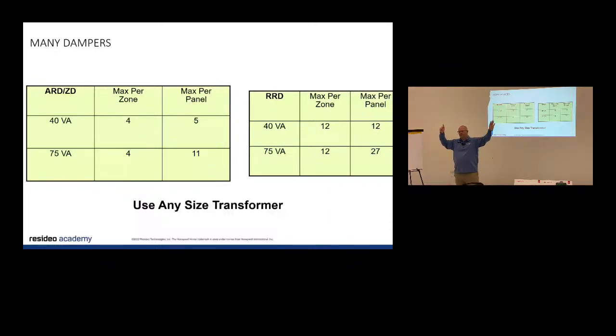And you got one thermostat upstairs, the basement's always cold, or your heat all drops to the basement if you have an open stairwell or whatever. So what heating guys do is they put two sets of ductwork in the basement, one for the basement, one upstairs, and then we put our dampers in, and you'll see some damper examples in a second. So the basement calls, upstairs shuts, and the furnace takes care of just the basement. Or I got upstairs and I gotta satisfy, and I don't really care because my basement's probably 6 degrees cooler than upstairs. I have an upstairs call, I shut the basement zone ductwork off, and I put all of my heat upstairs. That's the ultimate in comfort, and it's normally done during new construction.